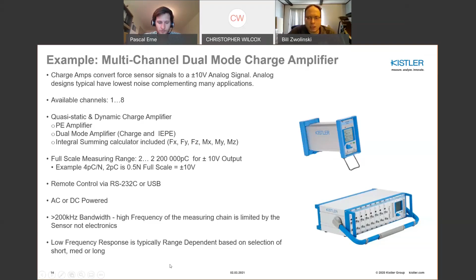What a charge amp does is basically takes the piezoelectric signal and converts it to a representative 10 volt, plus or minus 10 volt signal. The bandwidth of a charge amp typically is quite wide, so it's probably rare that you'll ever see that the high frequency characteristic of a force limiting test would not be covered by a charge amp. But you always want to check and pay attention to the low frequency, because not all charge amps are created equally in that regard.